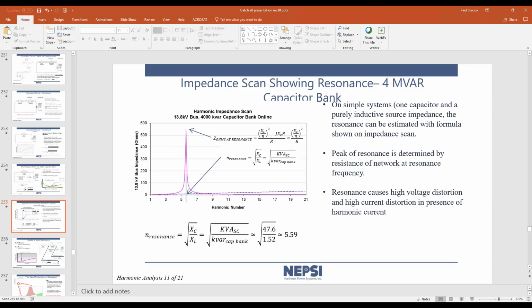The other thing to realize about these impedance scans is that you could potentially look at this impedance scan and say, well, I don't have a 5th resonance and I don't have a 7th resonance, and the data put out by EasyPower in, say, the IEEE 519 table would show that your distortion might not be high. But by viewing this impedance scan, you would say, oh, I've got a resonance near the 5th, and a resonance near the 7th, but it's not on the 5th or the 7th. And in this case, you would have concern, because if a slight change in system impedance were to occur, say the short circuit level was higher or lower than what I modeled, then I could potentially have a 5th resonance or a 7th resonance.